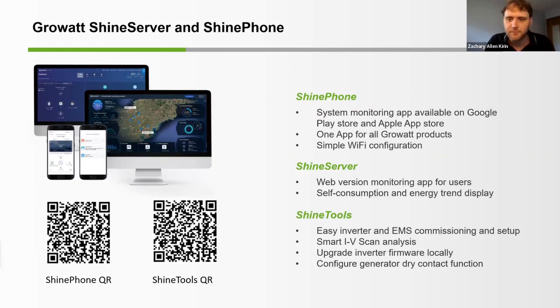The Wi-Fi communication is simple to set up. It can be set up on a 2.4 gigahertz Wi-Fi band, or using 4G communication, which comes standard for some MIN inverters. So the 4G communication would be purchased separately, but we'll explain a little bit more about that too. The 4G application allows the inverter to have a redundant method of sending data. This is very important because if the customer changes their Wi-Fi password, if they change out their router, or do anything like this and they lose communication with the inverter, it's not going to be affected if the customer had the 4G model. This way, when the Wi-Fi is lost, the 4G model switches over, only communicates via telecommunications, and this allows for redundancy.